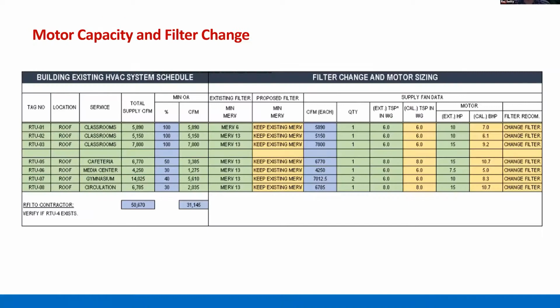The chart we have here: currently we're doing about 50 million square feet across an entire school system of filter changes. So what we've done is simply develop a basic spreadsheet to automatically tell you what the new MERV filter can be. The way the design engineer does it, they calculate a static pressure, then follow the fan curve and figure out the motor horsepower. Let's just say it's 7 horsepower, then we round up to the next frame size at 10.